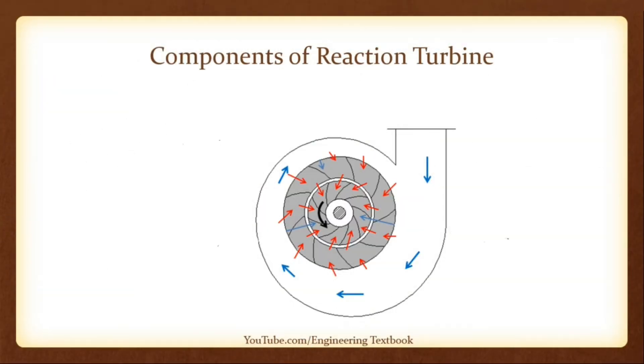Components of Reaction Turbine — Spiral Casing. It is a spiral casing with uniformly decreasing cross-sectional area along its circumference. Its decreasing cross-sectional area ensures uniform velocity of water striking the runner blades. As there are openings for water flow into the runner blades from the very start of the casing, pressure would decrease as it travels along the casing. So the cross-sectional area is reduced along the circumference to keep pressure uniform, thus ensuring uniform momentum and velocity striking the runner blades.